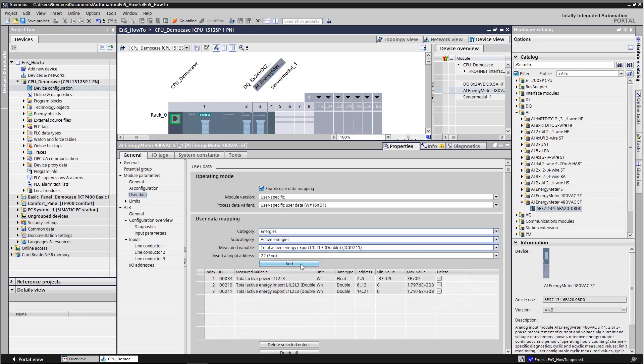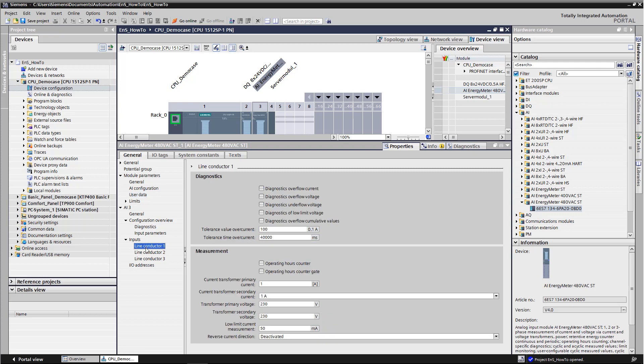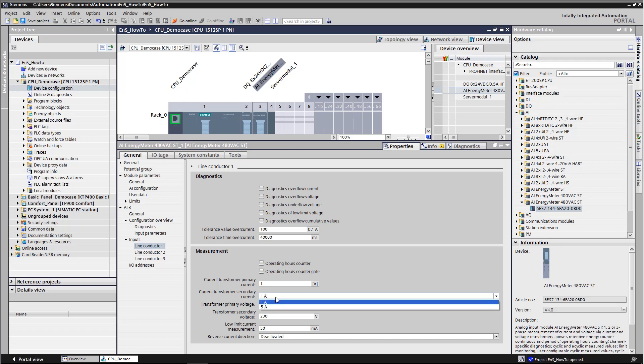If further data is required from the energy meter for user specific applications, this can be added below. The energy meter can only be used with a current transformer. In the item Input Line Conductor, the transformer for current and voltage can be set, primary and secondary. The configuration of the energy meter is now completed.